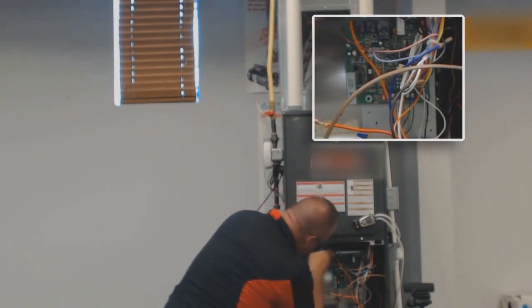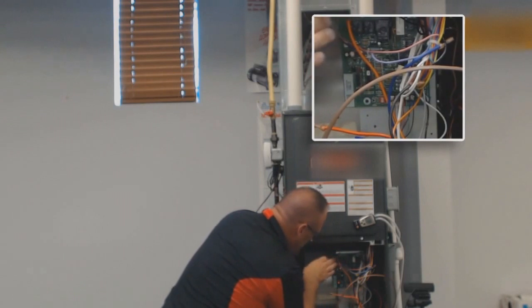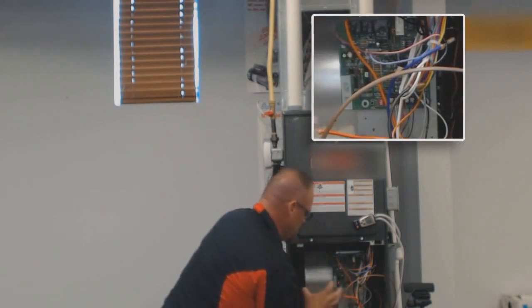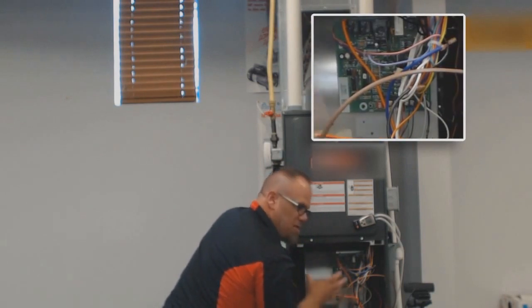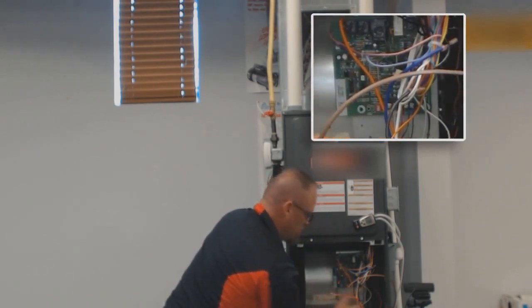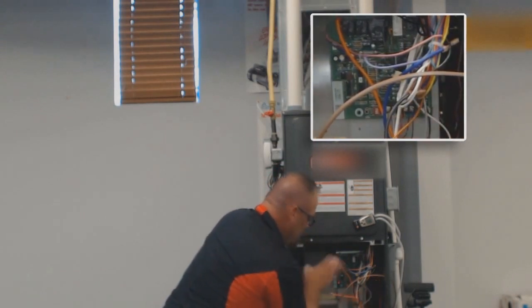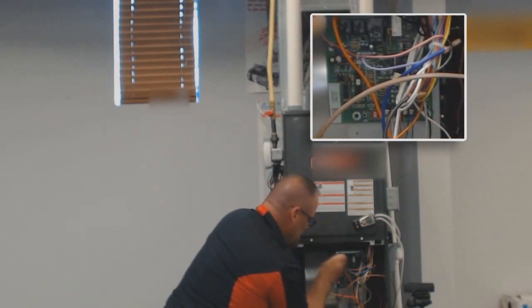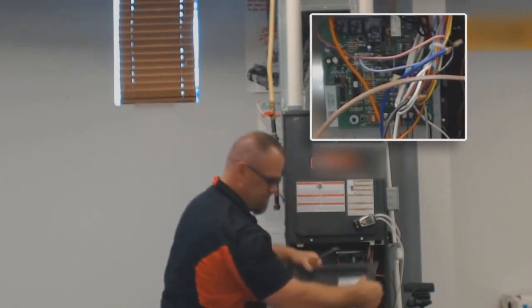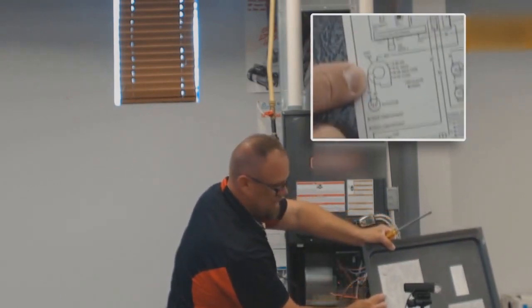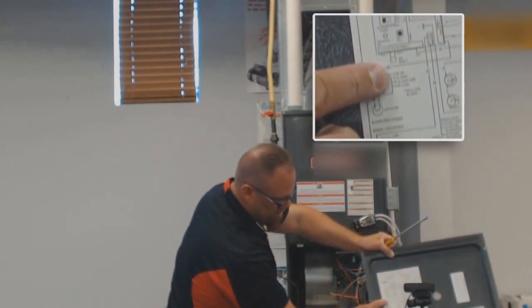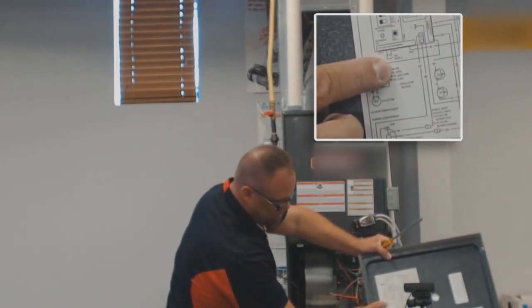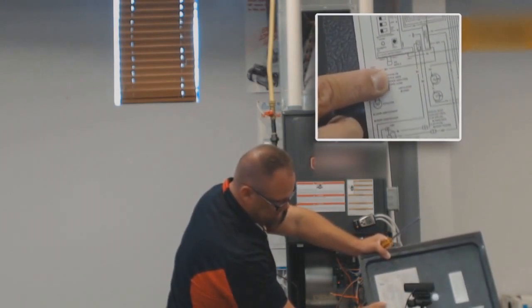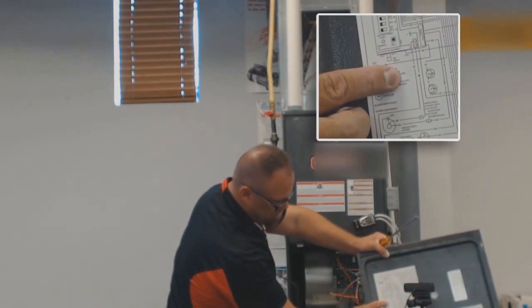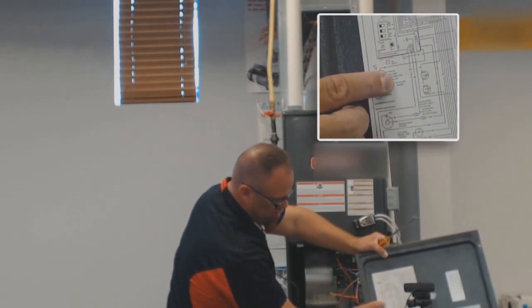Okay, so we've got several different areas where things hook up on this board, but what we're most interested in on this particular setup, where we've got a multi-speed blower, not a variable speed, there's no computer modulating system on the end, but just a regular multi-speed blower, we're going to change the speed taps, which will change the speeds. If you'll notice, right on the back of the data plate, we actually have the different speeds and the colors that correspond with those. Black is your high speed, blue is your medium speed, orange is your medium low speed, and then red is going to be your low speed.